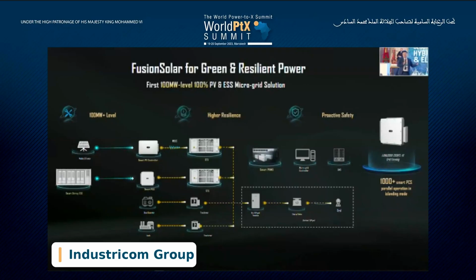For the Huawei battery container, we have multi-level protection from the battery cell level, battery pack level, with a battery pack optimizer to realize fault isolation between different battery modules. We have DC-DC per rack, 6 racks per container, for rack level shutdown and protection. Then finally, the container level, the whole system level.